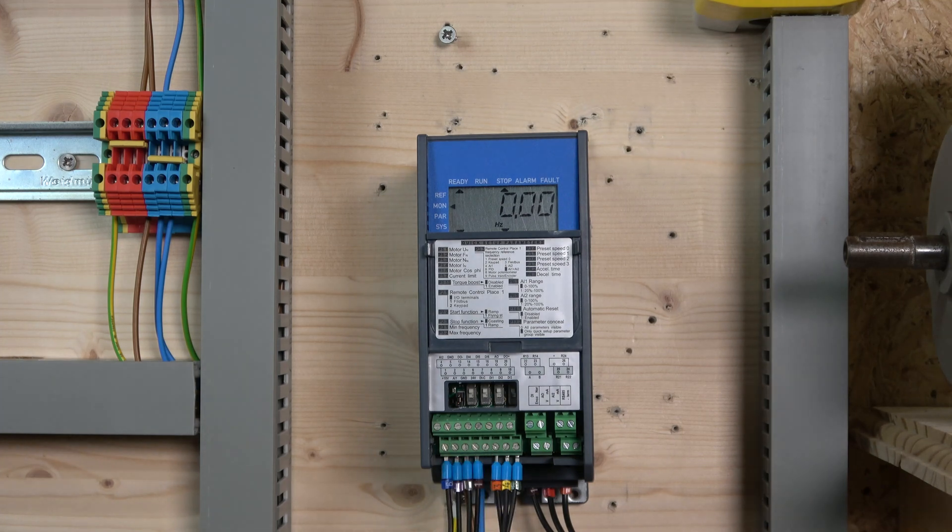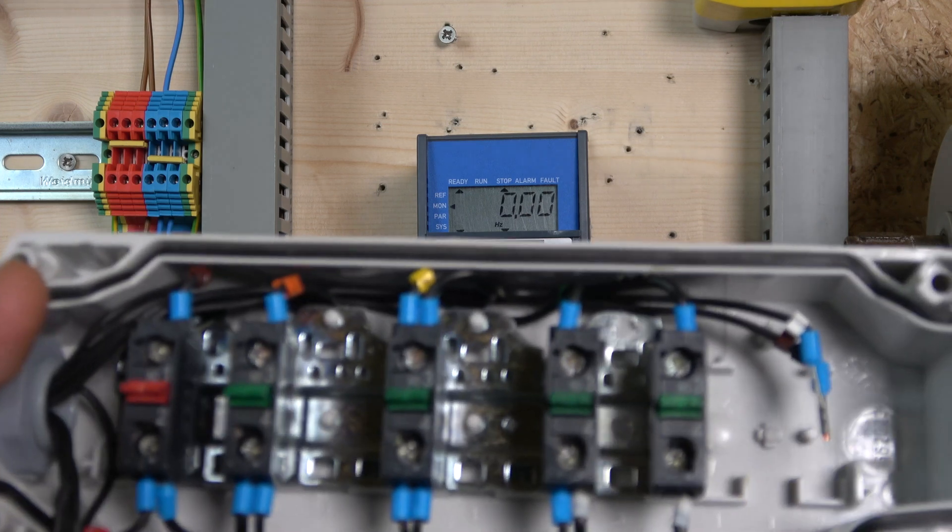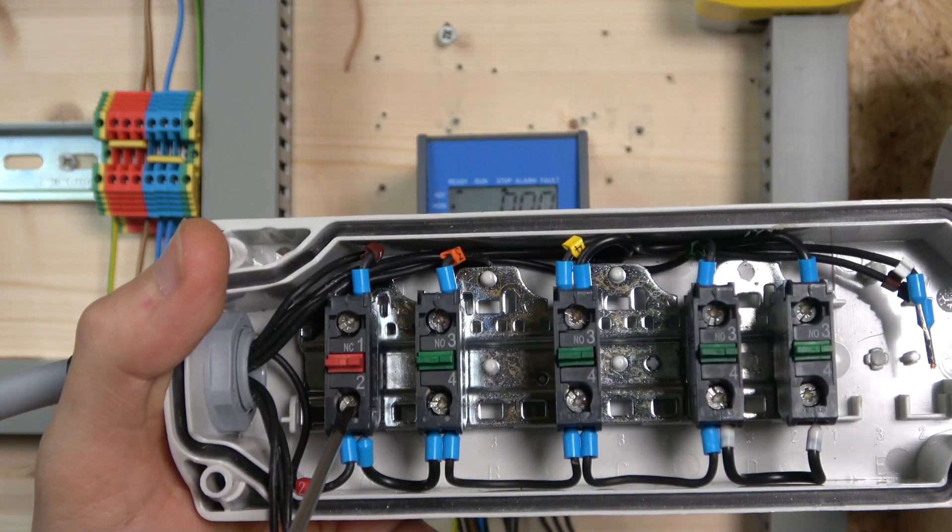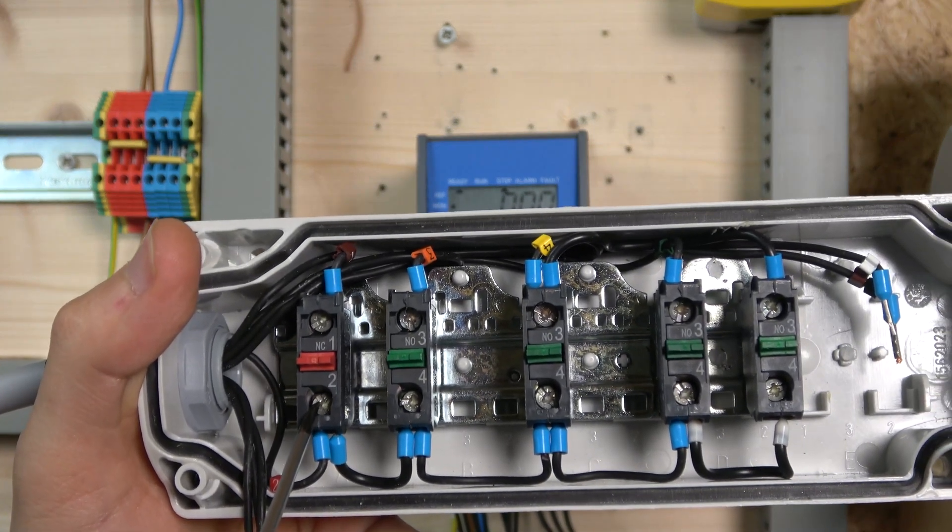To figure out which terminal is which, you have to count them since the numbers aren't clearly marked - a big no-no for me. Terminals one, two, and three are for the potentiometer. The fourth one is a 24-volt signal which goes through the e-stop switch and sends power to all the I/Os here and normally open contacts.